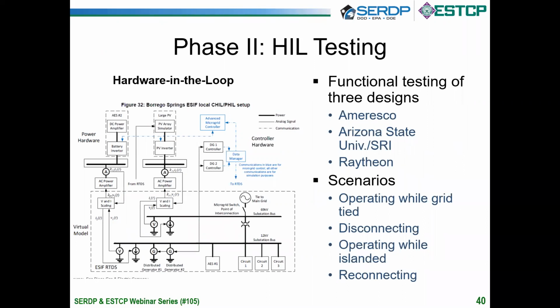We will actually include a diesel generator and its controller as actual hardware with power flows and comm links between them. And then you can emulate those elements which you can't have in a laboratory building setting: the full grid effect, the feeder design and its response, as well as the loads and the actual power coming from the full-scale PV. And these can be established in a hardware-in-the-loop facility, which allows you to run in real time the performance of your controller and your inverter and battery hardware.